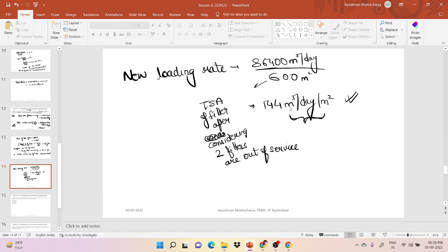New loading rate will be the total treatment capacity which the plant has, divided by the total surface area of the filters after removing the two filters. So if we divide 86400 by 600, this is the total surface area of filters after considering two filters are out of service. So new loading rate will be 144 meter cube per day per meter square. Is it clear now? Yes, sir.